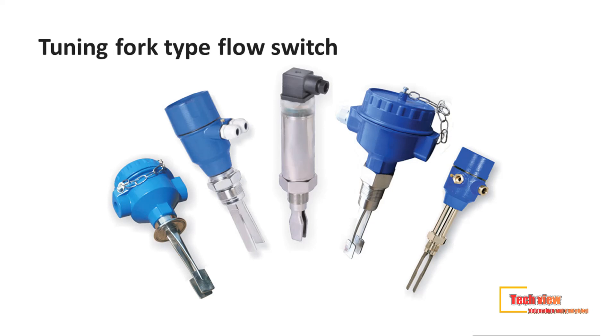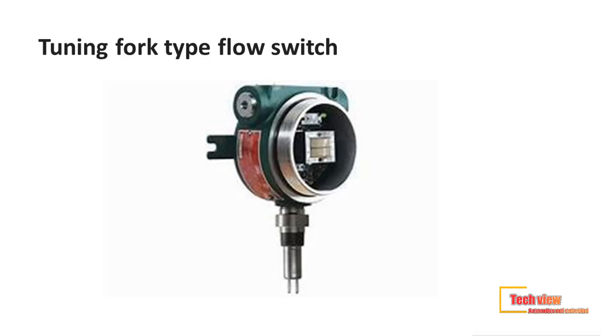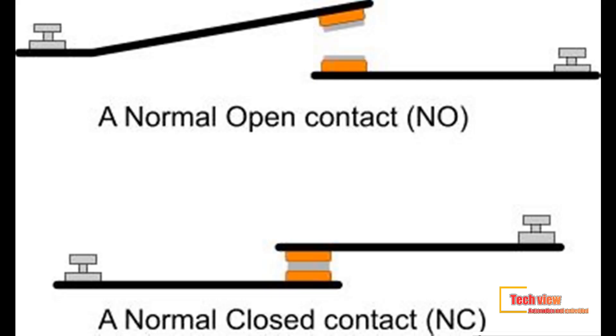The vibrating fork type flow switch uses a tuning fork shaped sensing element with two tines inserted into the bin or tank where the target media will be present. The tuning fork sensing element is placed into vibration at its natural resonant frequency by establishing motion in the sensing element or fork. The harmonic vibration of the tuning fork sensing element is established using piezoelectricity.